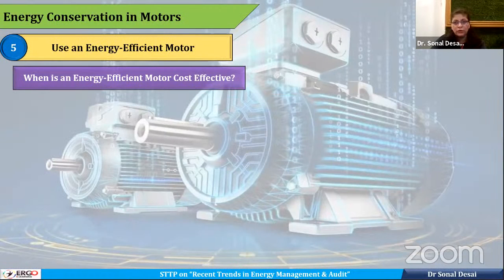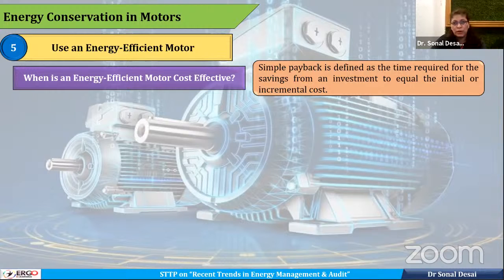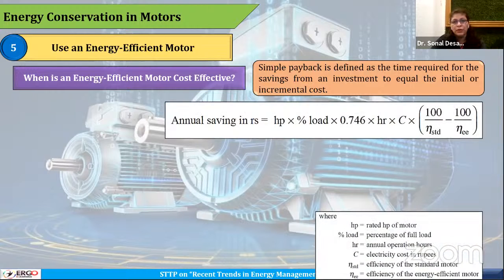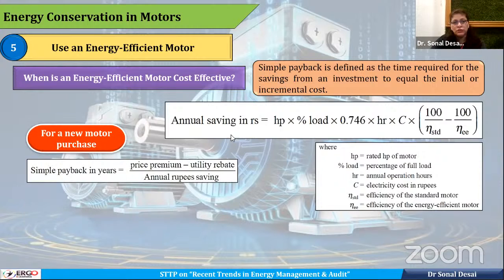When is an energy efficient motor cost effective? That is shown by this example. This is the equation showing annual energy saving: the HP, that is the rating of the motor, multiplied by the load at which it is operating, a factor to convert HP to kilowatt, hours of operation, electricity cost of the company, and the efficiency of the standard motor versus the efficiency of the energy efficient motor.